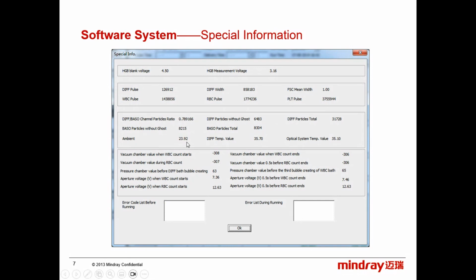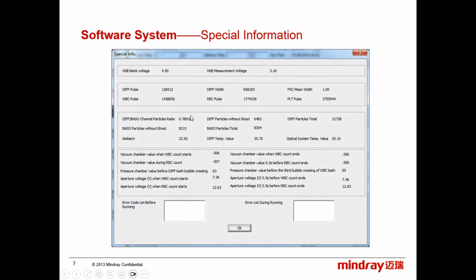This is the ambient temperature during the test, the diff temperature, and the optical system temperatures. Okay, and this is related to voltage, aperture voltage, vacuum, and so on. So it's very important. During the troubleshooting, I will choose some abnormal results, and we'll see how reading or understanding this special information can help us in finding what the problem is.